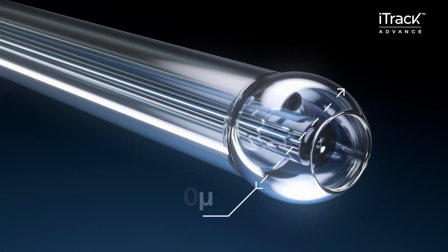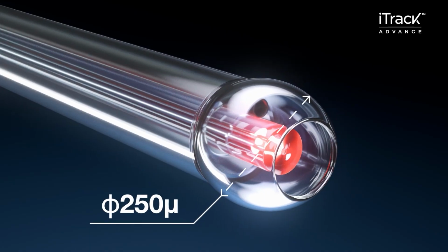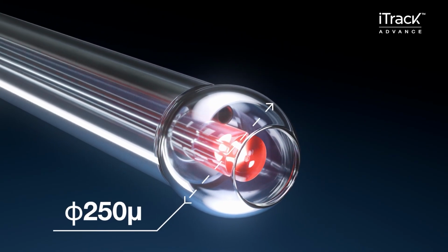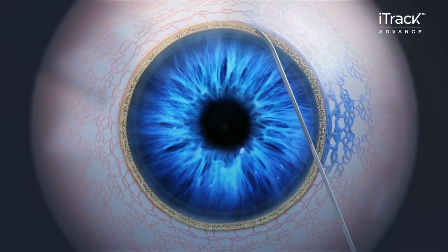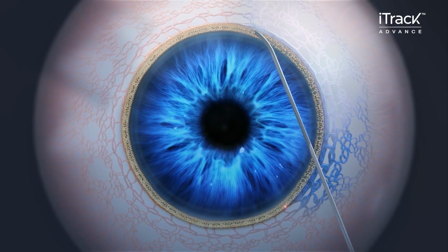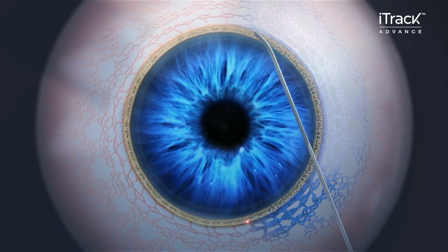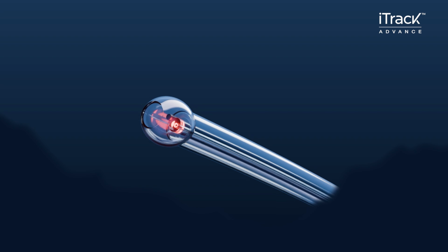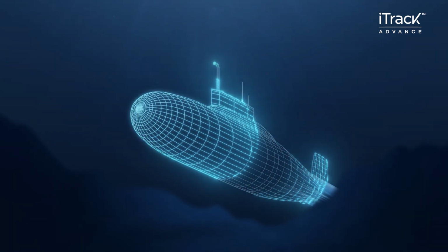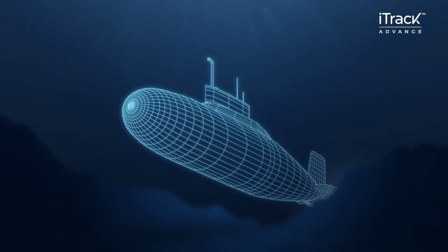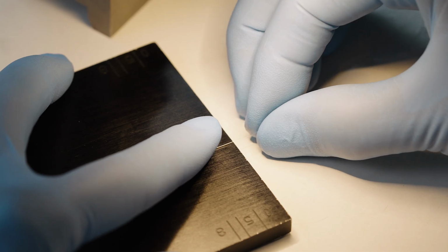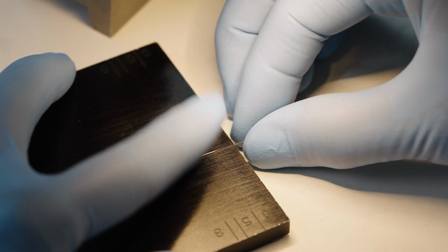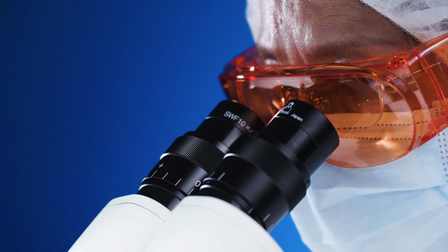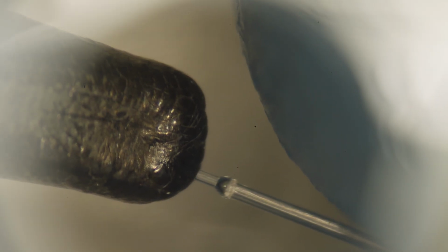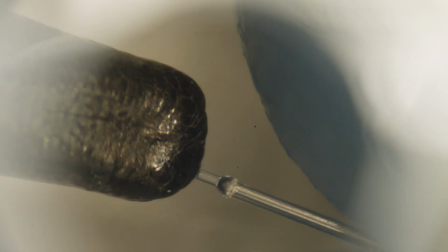The tip of the iTrack Advance is slightly larger than its shaft at 250 microns. And even at this scale, a simple flat edge can snag and damage the delicate wall of Schlemm's canal. That's why the tip of the iTrack Advance is engineered like the rounded nose of a submarine, designed to glide with minimal disturbance. Each one is individually fashioned by hand under a microscope, creating a smooth, bulbous shape that doesn't pierce a path, but gently displaces tissue as it traverses the canal.